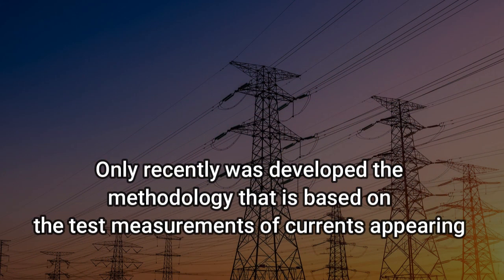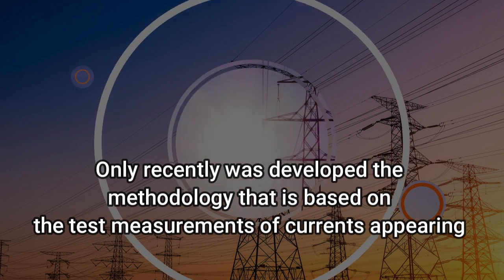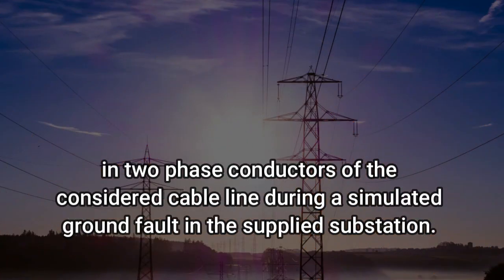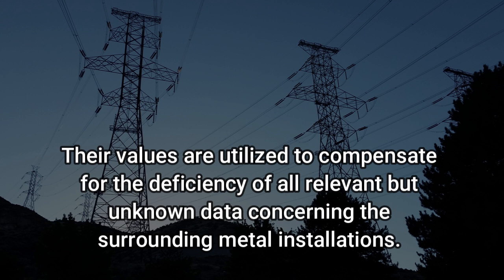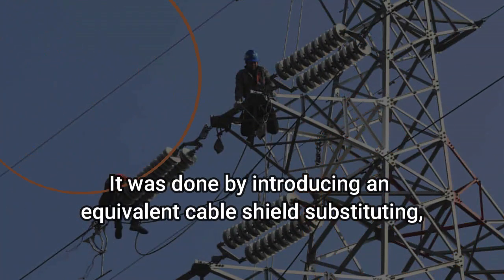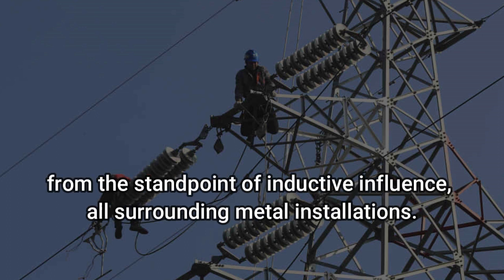Only recently was the methodology developed that is based on the test measurements of currents appearing in two phase conductors of the considered cable line during a simulated ground fault in the supplied substation. Their values are utilized to compensate for the deficiency of all relevant but unknown data concerning the surrounding metal installations. It was done by introducing an equivalent cable shield substituting, from the standpoint of inductive influence, all surrounding metal installations.